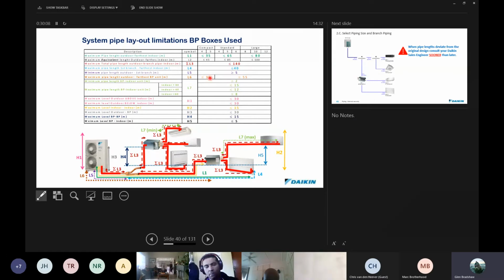Okay. And then the other one, the one that I wanted to chat to you about, was the length of BP boxes for indoor units with a capacity index of less than 60. Okay, so that would be like with a model number as a 60 in it or less. Okay, if they are greater than 60, they should be less than 15 meters. If it's equal to 60, 12 meters. Okay, and 8 meters for units smaller than that.